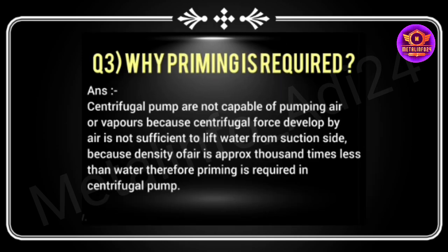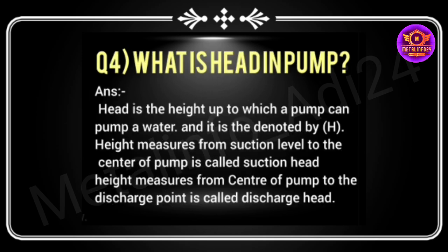तीसरा प्रश्न है, why priming is required? Centrifugal pumps are not capable of pumping air or vapor because centrifugal force developed by air is not sufficient to lift water from suction side because density of air is approx 1000 times less than water. Therefore priming is required in centrifugal pump.